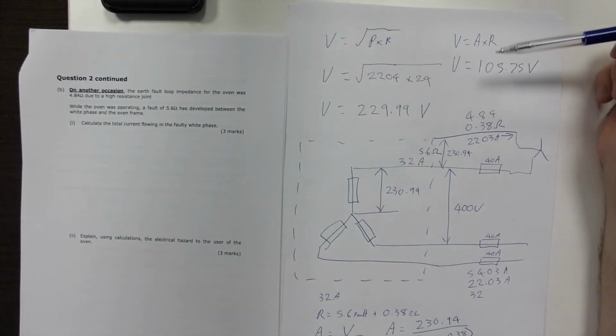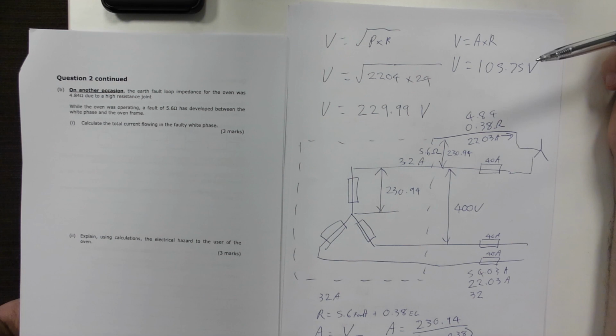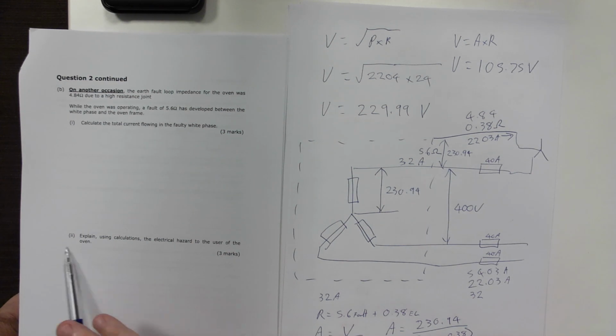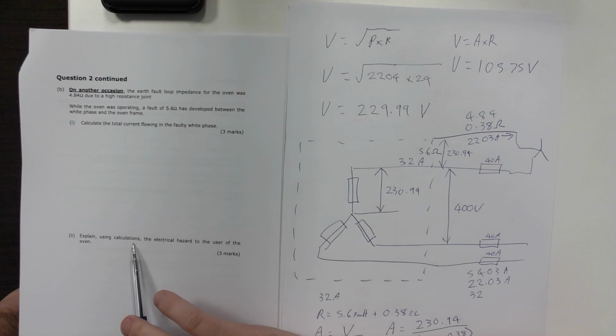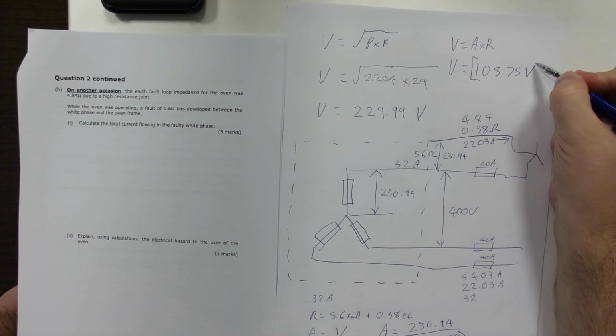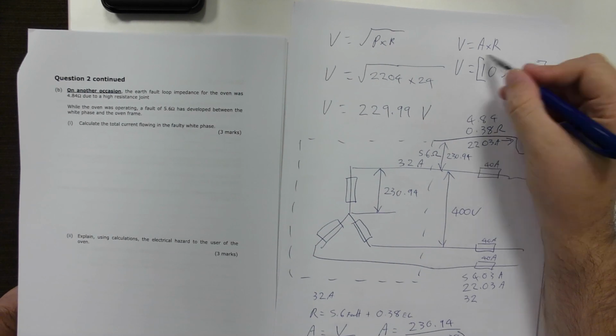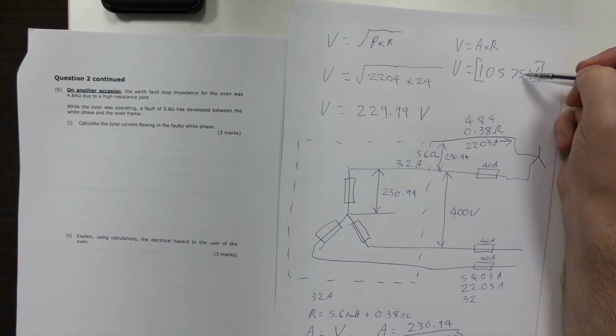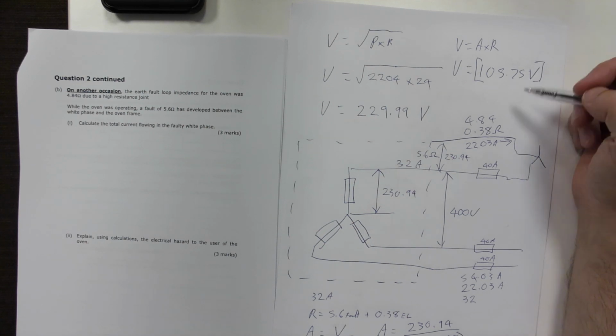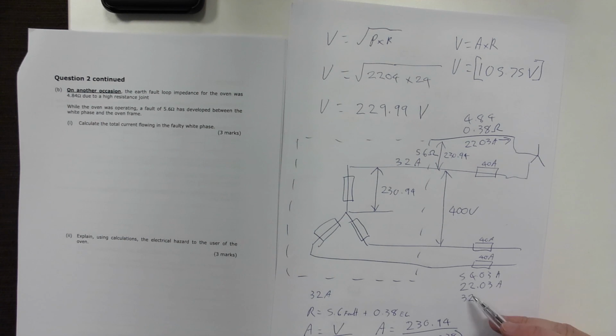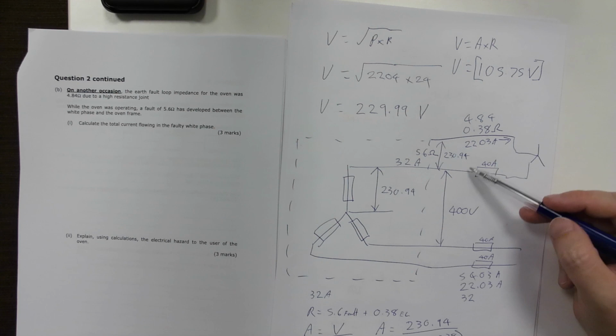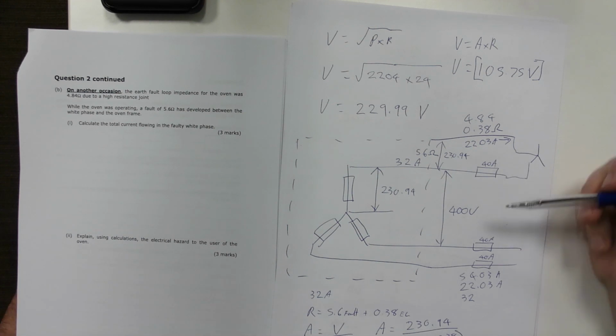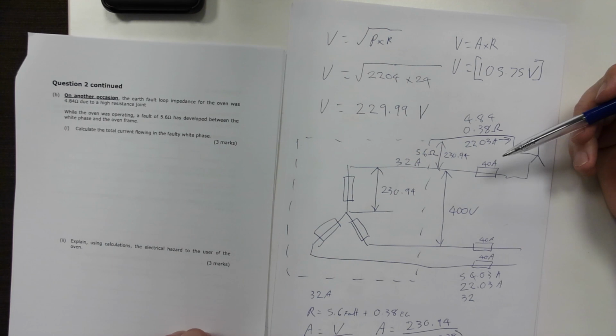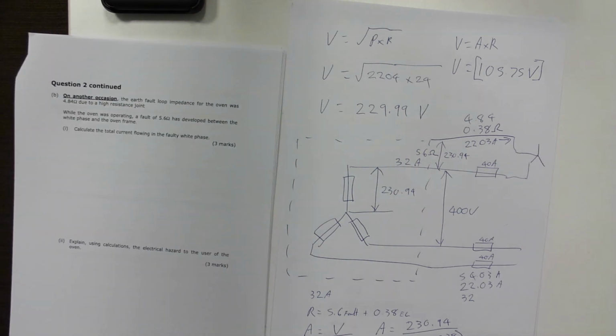This is enough voltage for you to feel. So that's the thing we're next doing in question B2. It's explain using calculations the electrical hazard to the user of the oven. The electrical hazard is it's not going to trip because you've got 105.75 volts for the person to feel, and the actual current flowing, because we've got 22 plus 32 is 54 amps, and these require 60 amps to even start melting. That's never going to disconnect the supply. And now we're on to question 3.